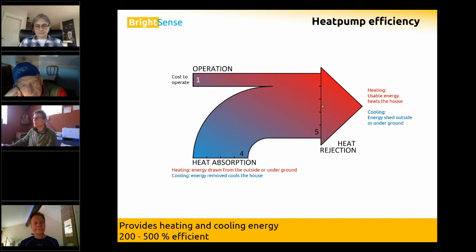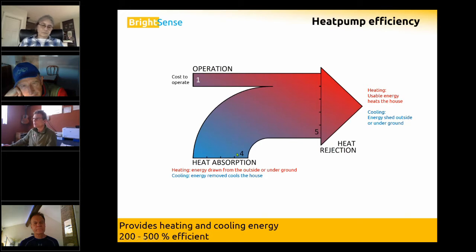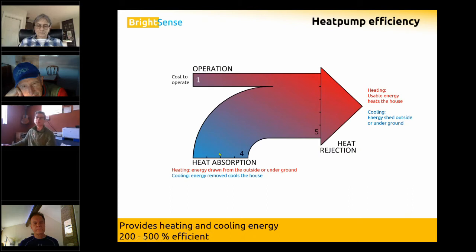When we put the usable energy in relation to what we pay for — one unit of energy to operate — five units of usable energy for heating would be 500% efficient. If we're cooling and getting four usable units of cooling energy, our coefficient of performance would be 400%, four to one.